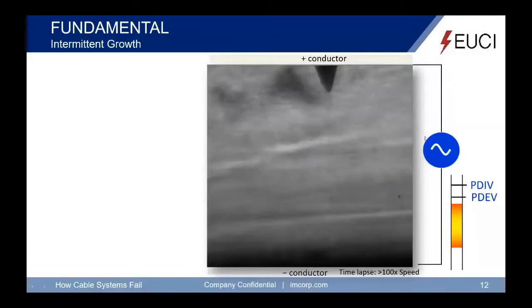So here we're going to show you some growth of a cable. Here, this is a pin type. I'm going to try to move this again, see if I can get around it. There's a pin that we stuck in some insulation, at 100 times the speed. Again, we're going to look at partial discharge inception voltage as well as partial discharge extinguished voltage.